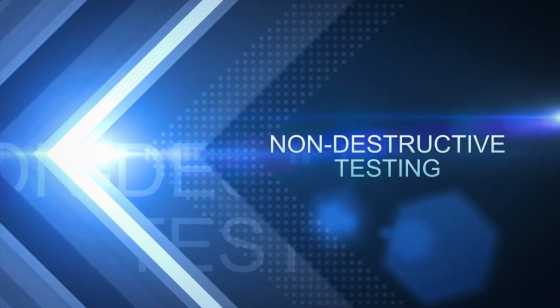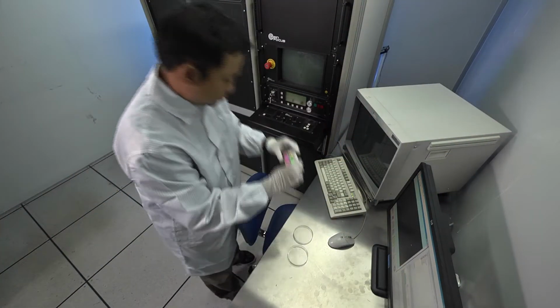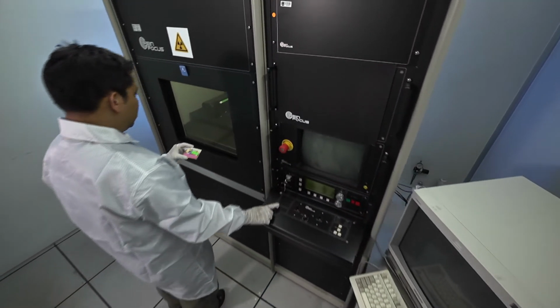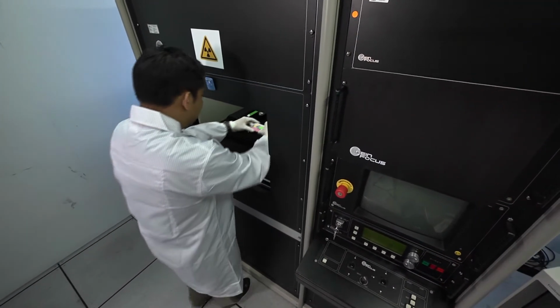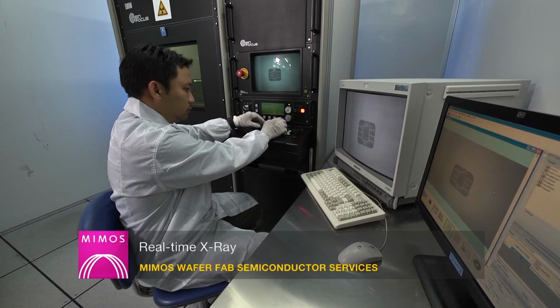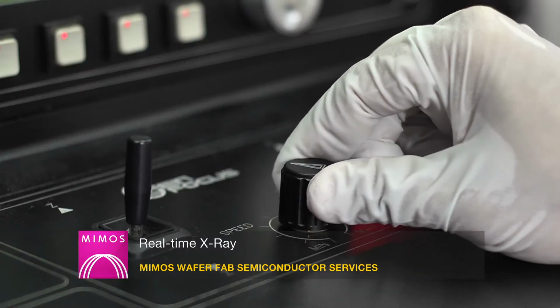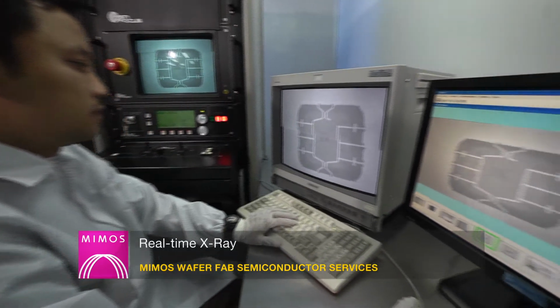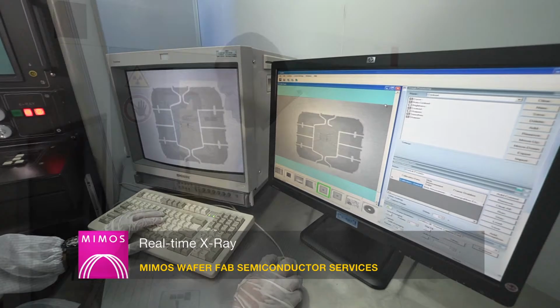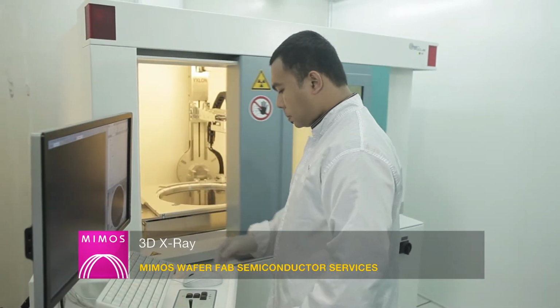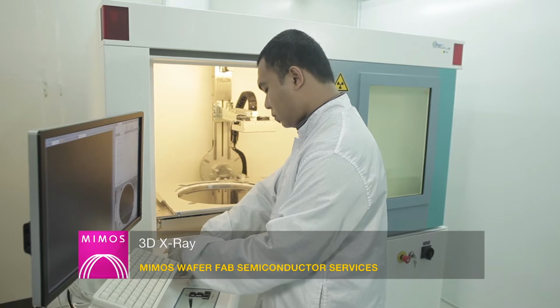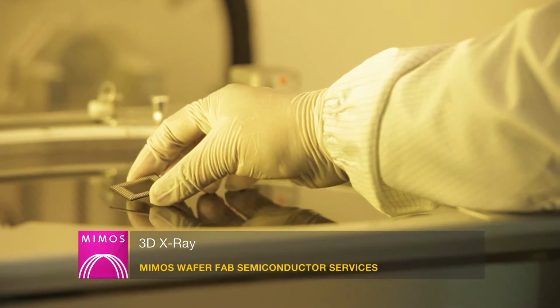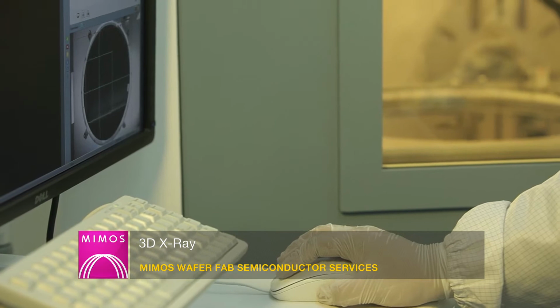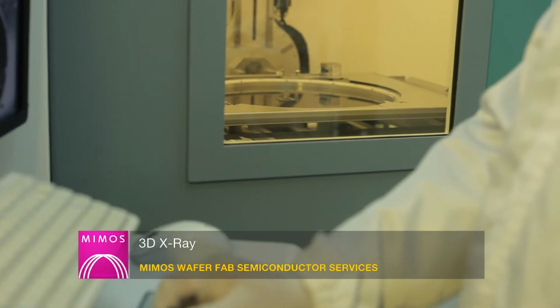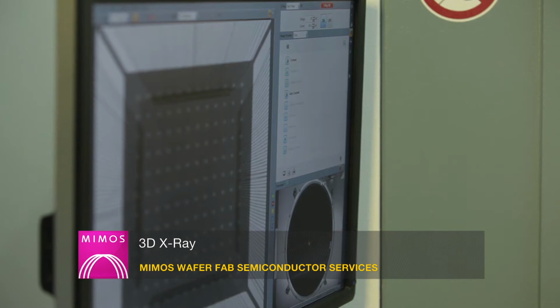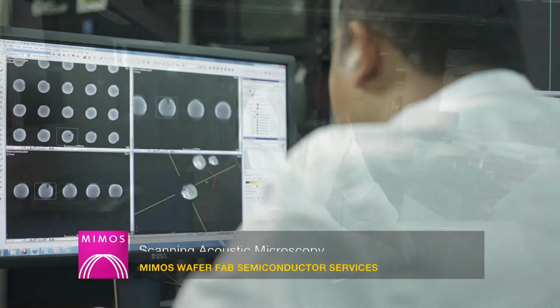Non-destructive testing is the first step towards defect isolation by determining the internal conditions of the sealed devices. Real-time X-ray inspection system is used to view the internal geometry, connections and physical conditions of the devices. 3D X-ray imaging is able to provide detailed information inside of a chip by using its 3D reconstruction capability. The system is able to give 3D virtual cross-sections, slices and measurements on a region of interest.